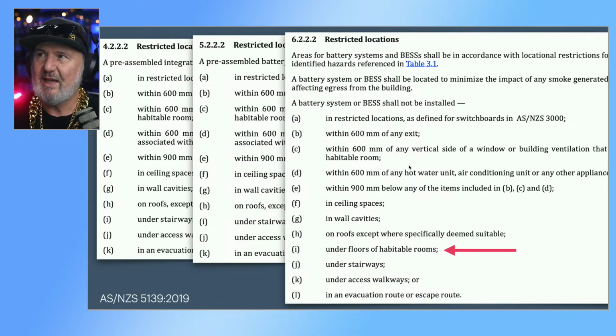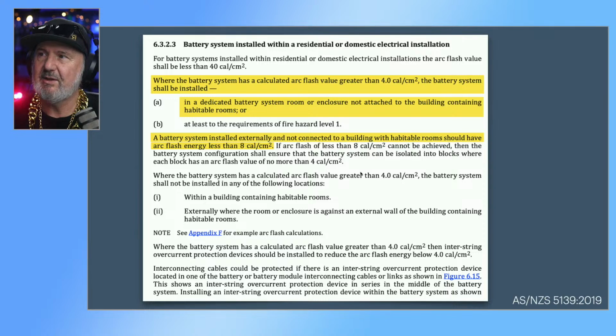But there's a sort of related clause. I think I've got my slides in the right order here. Yes, here it is. So for Section 6 batteries, we're focusing here on arc faults as well. With arc fault analysis, we calculate the prospective incident energy from an arc from the battery system. As you can see at the very top there, it says for battery systems installed within residential or domestic electrical installations, the arc flash value shall be less than 4.0 cal per square centimetre.